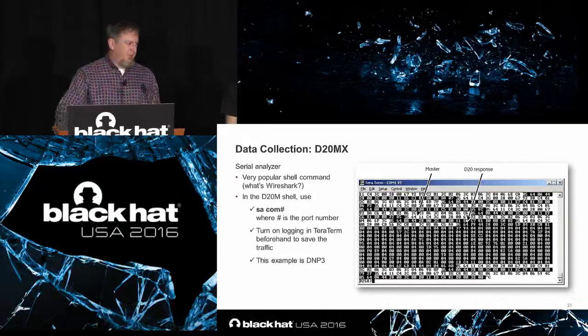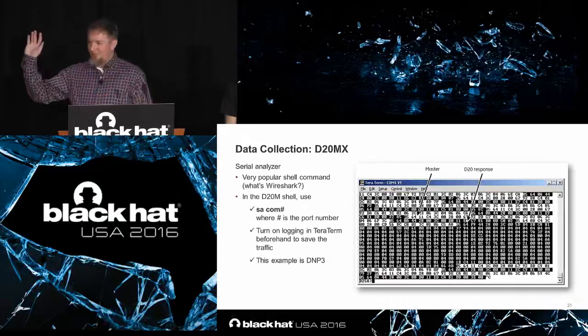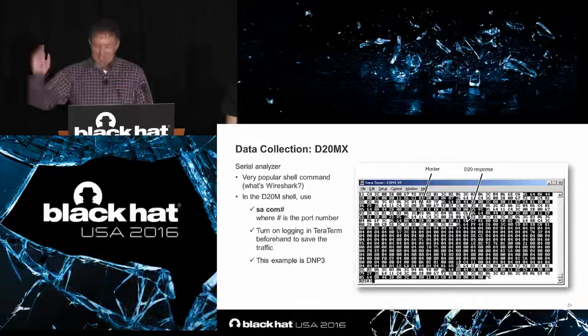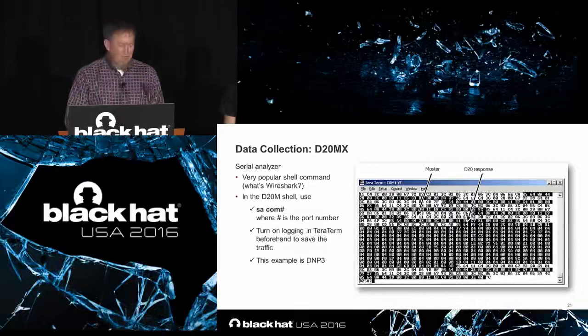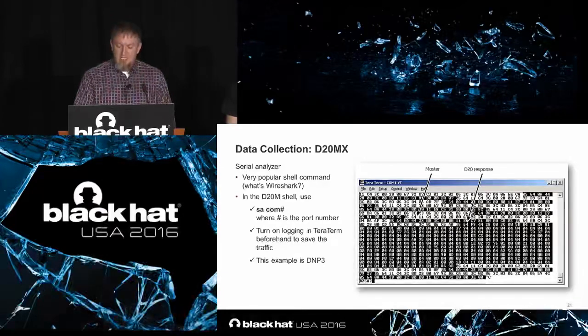Serial analyzer: how many people still use serial? Yeah. 1200 baud. So what's Wireshark? We can use the serial analyzer to look at the traffic, and this is an example of using DNP3 over serial, so we can do forensics that way.